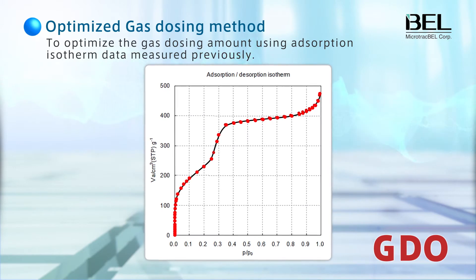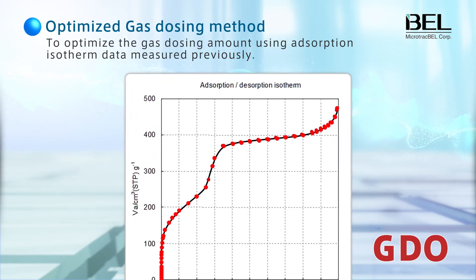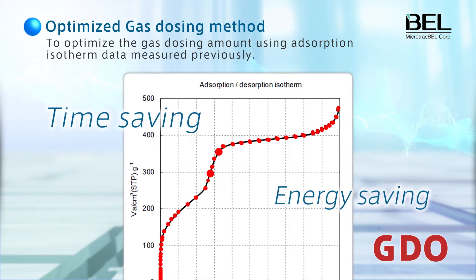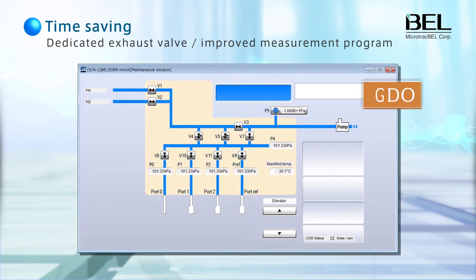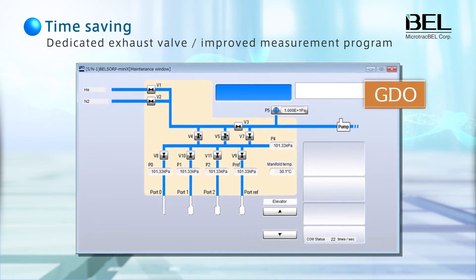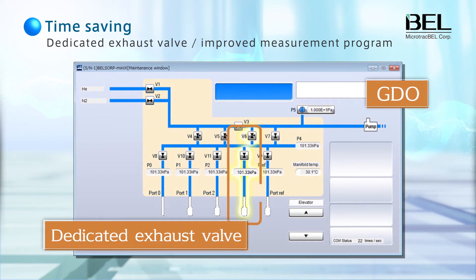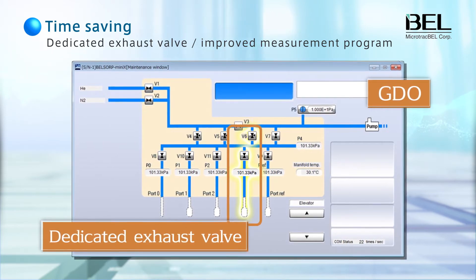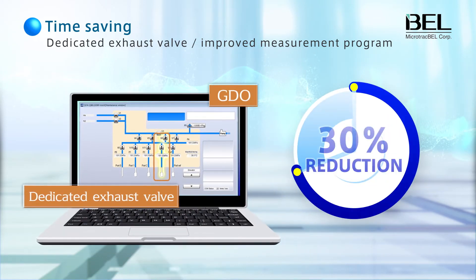When measurement points are insufficient, you can add them manually. The dedicated exhaust valve, GDO function, and new control software drastically shorten measurement times by up to 30%.